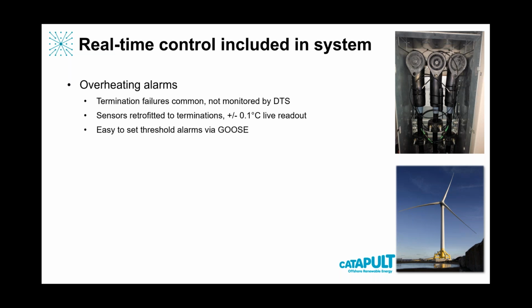Now, we also talked about real-time control in the same system. So once you've installed the sensors, which you'll have noticed we could retrofit a cable in a day, we're also able to, and we've shown here with OREC, that we've also put temperature sensors on the terminations themselves. This is a critical failure point, and failures are quite common. There are multiple causes of why the terminations overheat, but they do, and some of them can fail critically. And this is not monitored by DTS. DTS can't see these locations, so this is complementary to DTS and provides additional insight and visibility to the scheme.